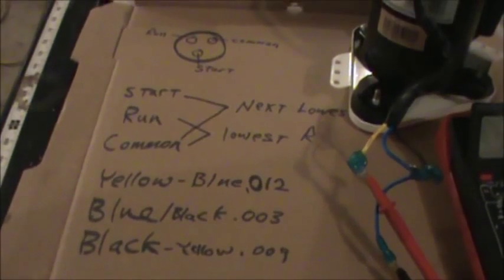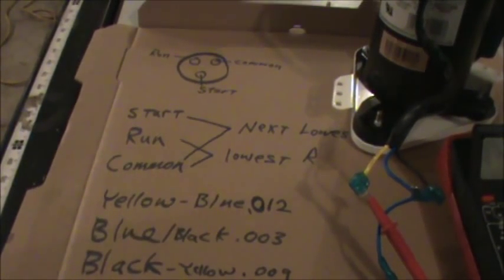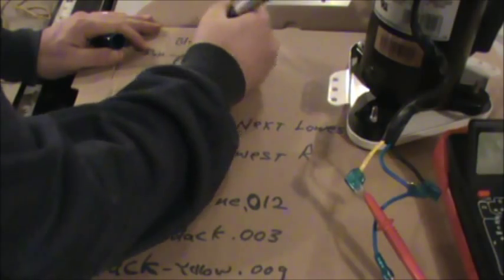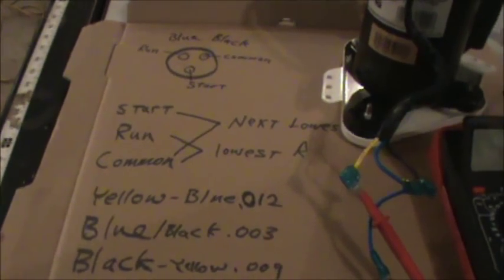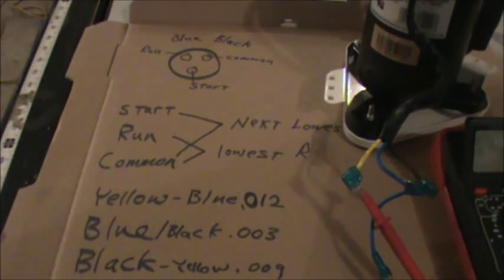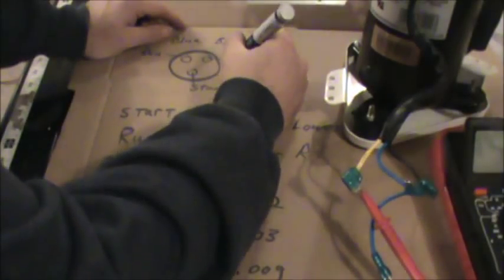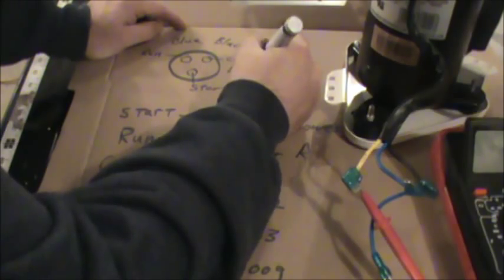We said that between run and common, that's going to be our lowest resistance. So we have blue and black, 0.003, that's our lowest resistance. So we're going to put those colors up top. We know that our lowest resistance goes between the run and the common, and the wire color was blue and black. And then we look at our next lowest resistance. Our next lowest resistance goes between start and common, and that's 0.009, black and yellow. So up here we know that these are going to be black, yellow.